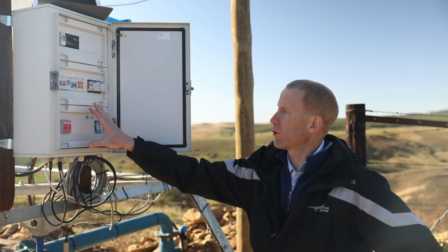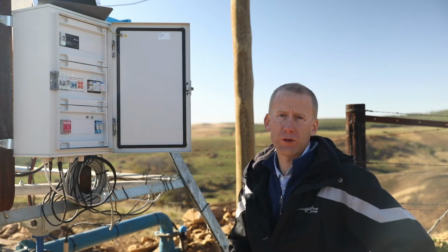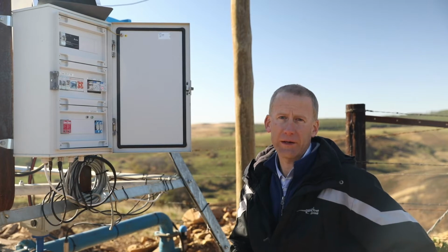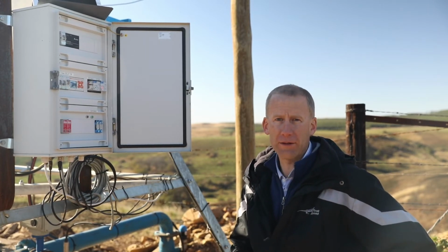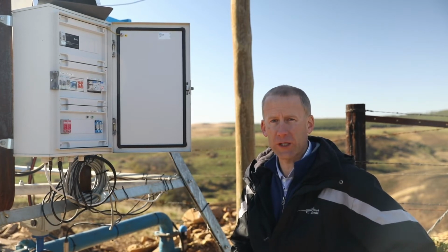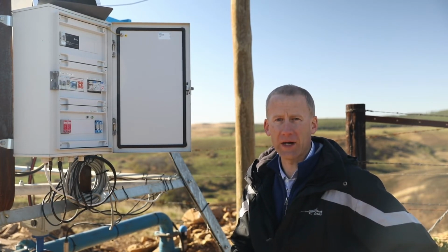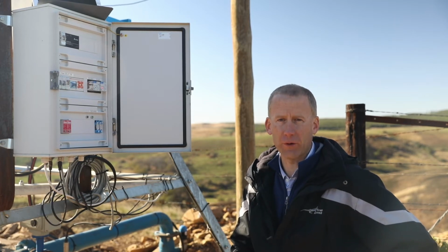The system has got a main control box which controls the timing of the Pivot and pods. During the day, it will open the valve for the pods, turn on the pump, run the pods at the correct pod pressure, and then at night it will shut off the pump, close the pod valve, open up the Pivot valve, turn on the pump and run the pump at the correct pressure for the Pivot.